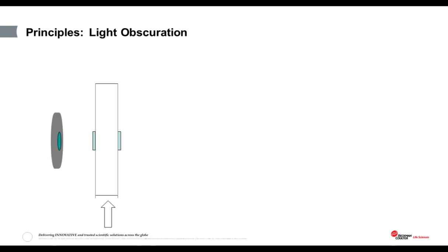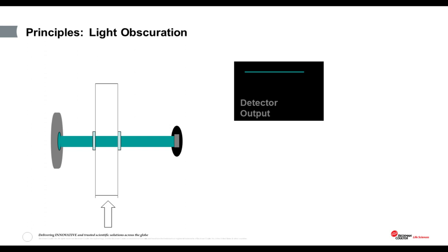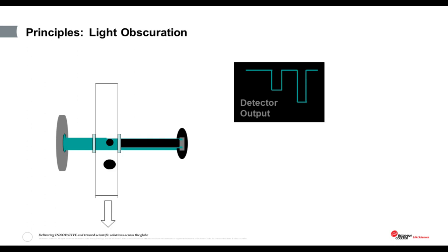Now, in a light obscuration counter, there's a light source, typically a laser, which illuminates through a sampling window in the flow path, and a detector on the opposite side of the window. And this detector turns the amount of light falling on it into an electrical signal, which can be measured. When particles pass through the measurement window, they partially block the light falling onto the sensor. And this reduces the amount of light falling onto the detector. The change in the detector electrical output is proportional to the size of the particle flowing through the laser light.